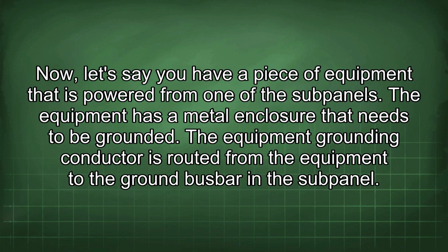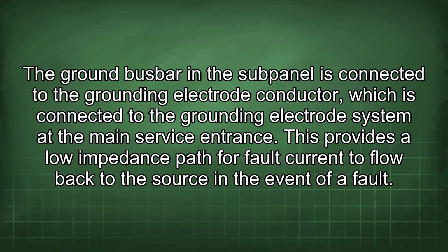Now, let's say you have a piece of equipment that is powered from one of the subpanels. The equipment has a metal enclosure that needs to be grounded. The equipment grounding conductor is routed from the equipment to the ground busbar in the subpanel. The ground busbar in the subpanel is connected to the grounding electrode conductor, which is connected to the grounding electrode system at the main service entrance.